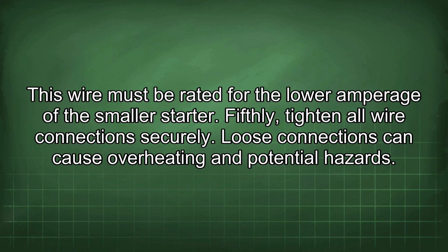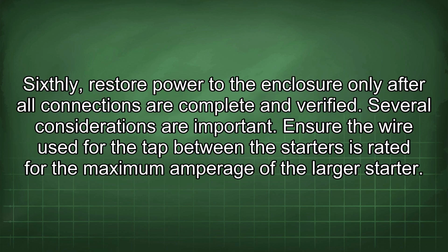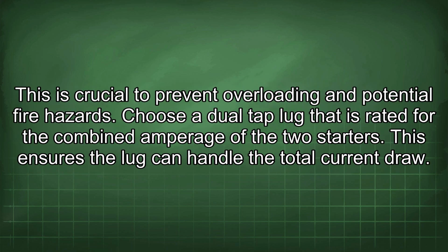Fifthly, tighten all wire connections securely. Loose connections can cause overheating and potential hazards. Sixthly, restore power to the enclosure only after all connections are complete and verified. Several considerations are important. Ensure the wire used for the tap between the starters is rated for the maximum amperage of the larger starter. This is crucial to prevent overloading and potential fire hazards.